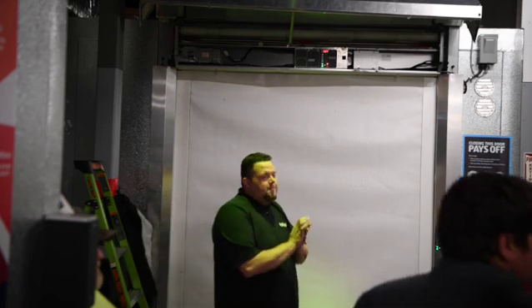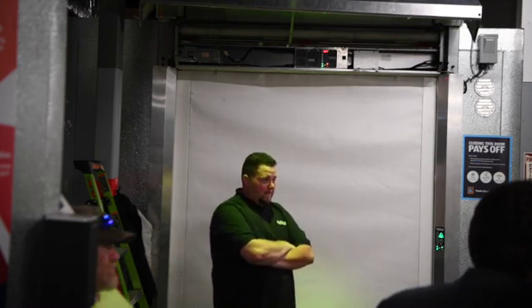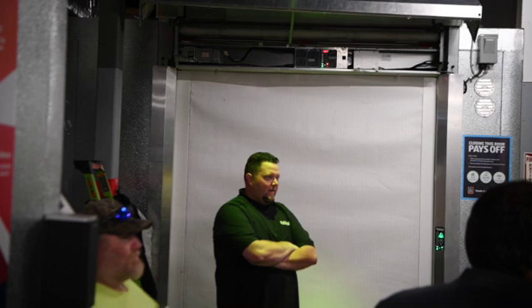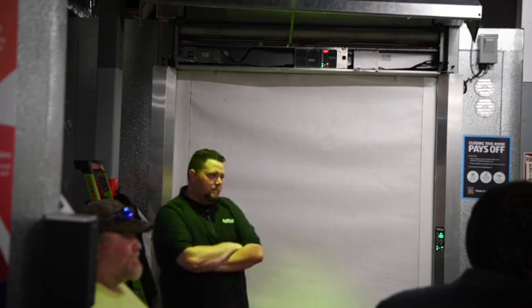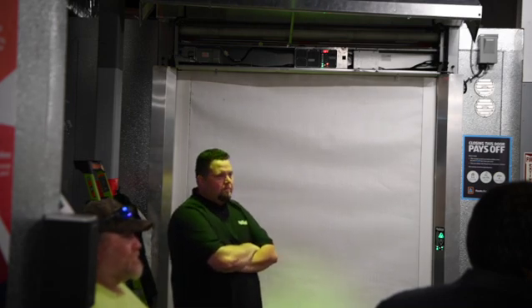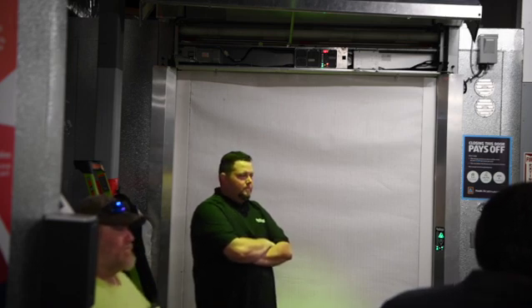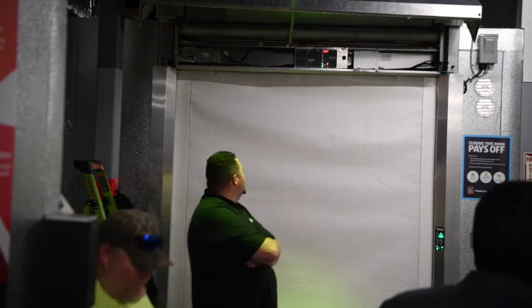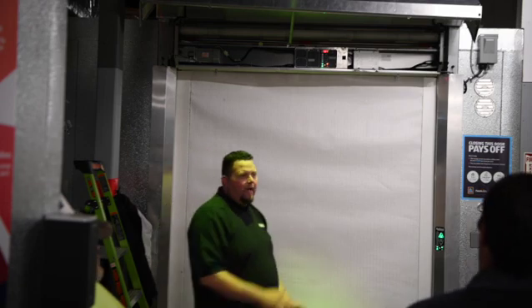You know, when we run into situations, and not to throw folks under the bus, Kroger's a good example. We'll go to a Kroger and somebody's gone up there to change that close setting to like 3 minutes, which is ridiculous on the freezer. What they don't realize is they're changing it to 3 minutes, but then every time you walk through it, it starts back over at 3 minutes. So it's not odd for that thing to sit there for 10, 15 minutes open. So we'll go change them back down, then they'll go change them back. So I'll change that back. I just wanted to make sure everybody knew what that was capable of.